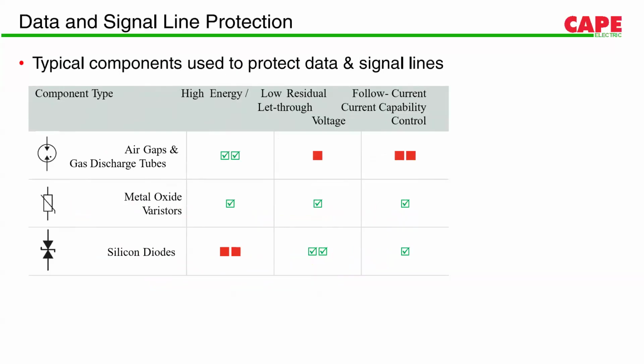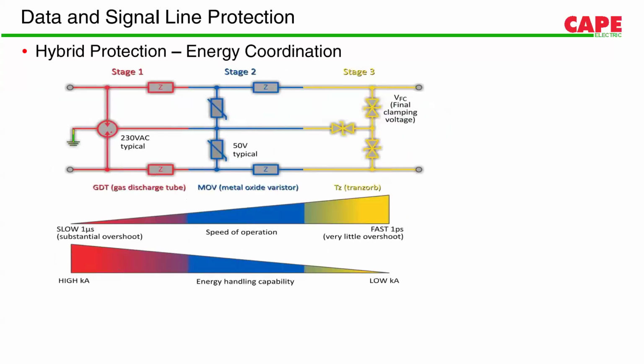So GDTs have very high energy handling capacity, mid or low let-through voltage, and very poor follow current capability control. Metal oxide varistors have decent energy handling capacity, low let-through voltage, and low follow current. Diodes have very low energy handling capacity, low residual voltage, and very low follow current. This is called energy coordination. This is a small graph which shows energy coordination.